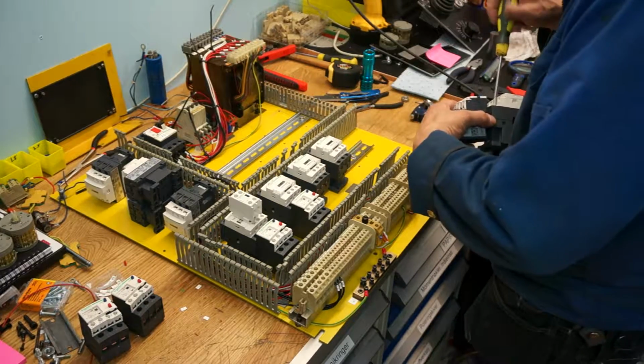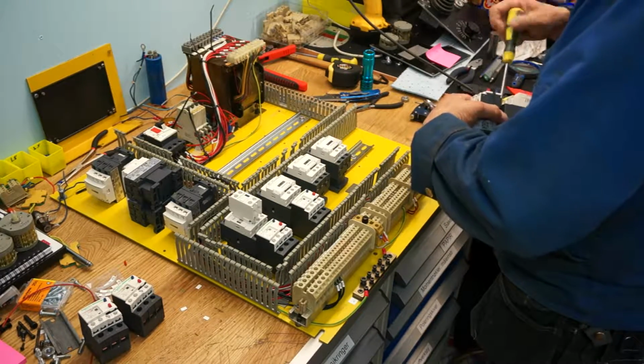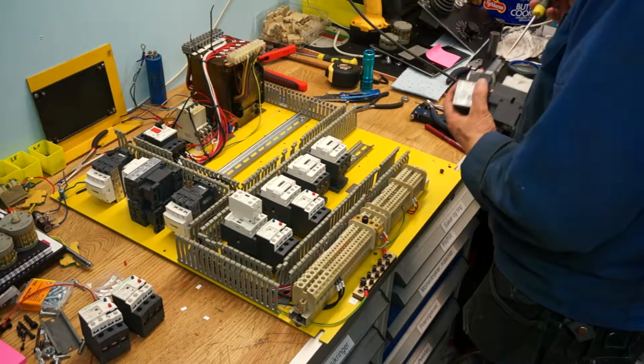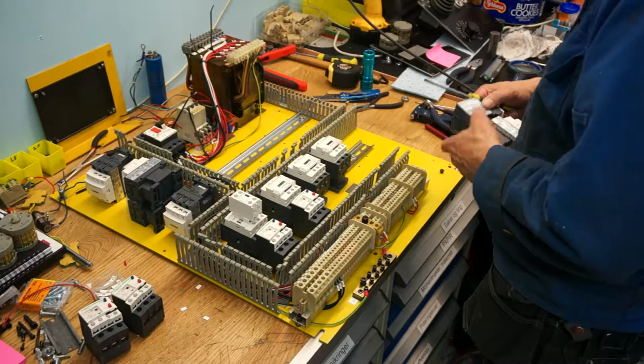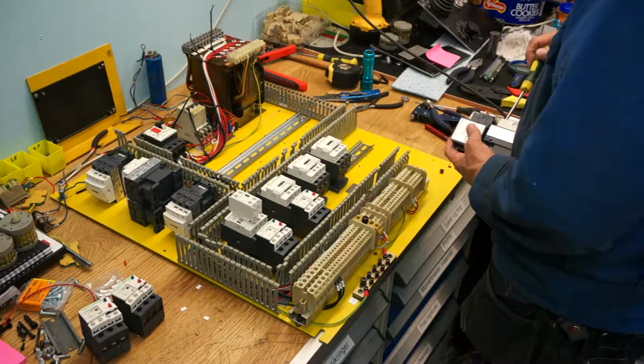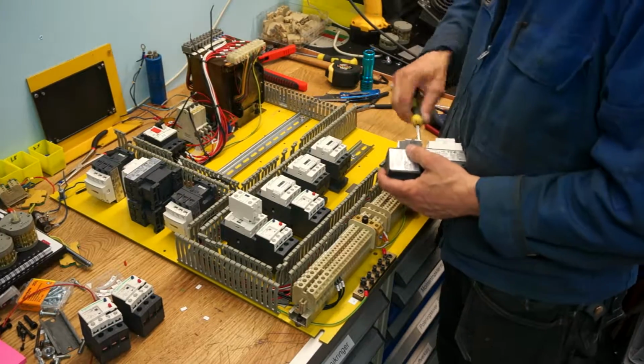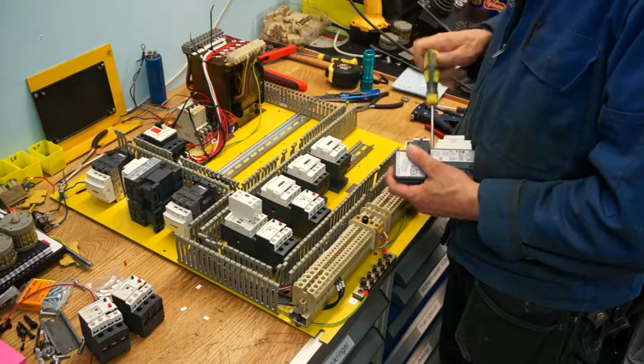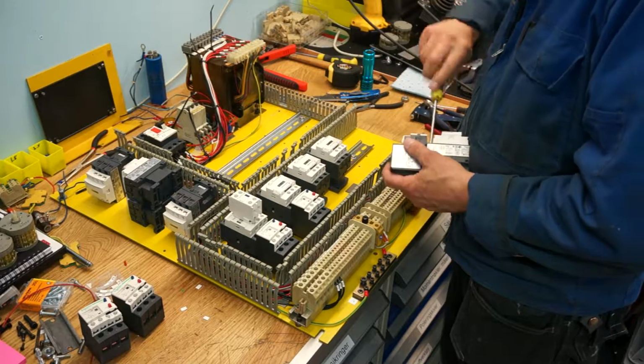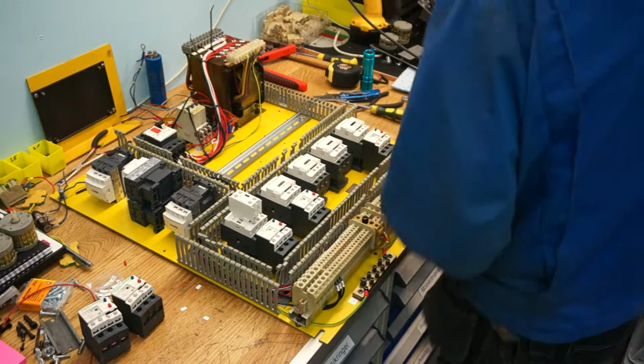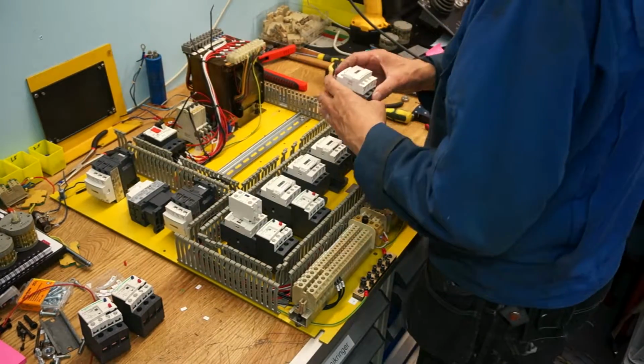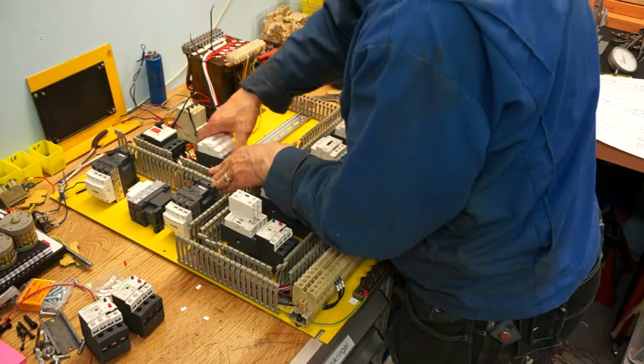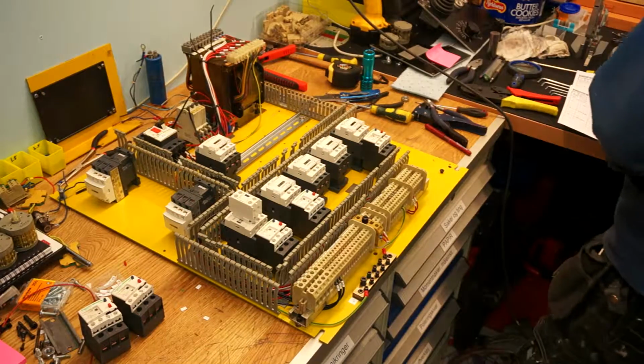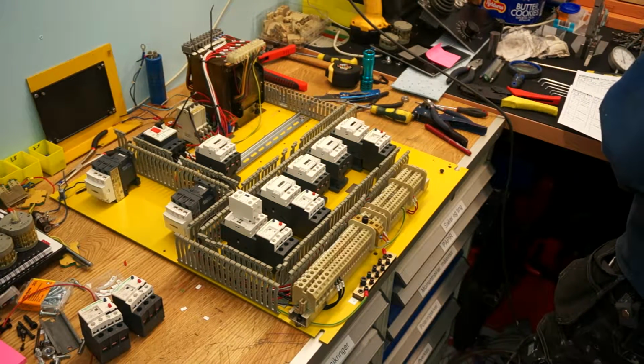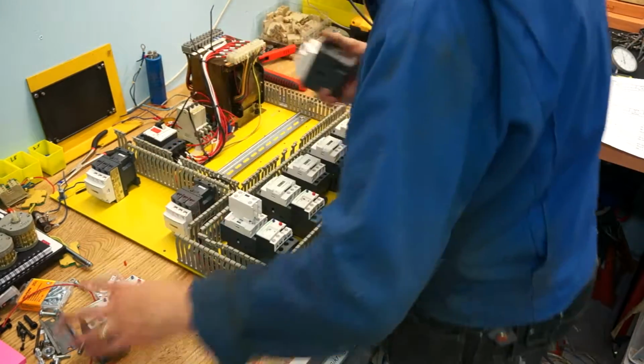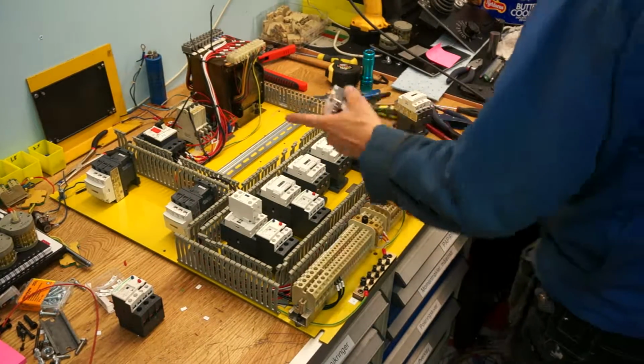The current passes from the contactor through the thermal relay, and these come in different ranges depending on the current you're supposed to draw, and you can also adjust within a range. These are particularly useful when controlling power to motors. Let's say a motor gets jammed or something like this - it will draw an incredible amount of current, and that will be detected by the thermal relay and it will shut off. So it's like a safety device for your motor.